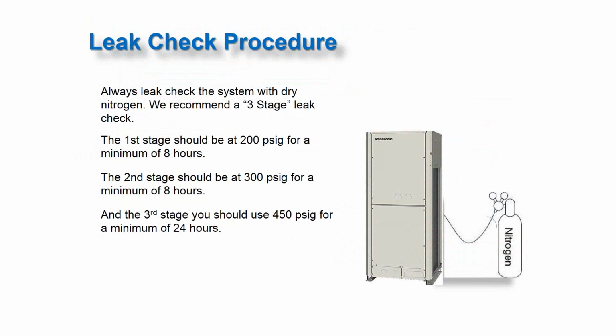Okay, leak check procedure. Very, very, very important when doing commissioning. When you're all done with your install, before you do startup, leak check your refrigerant pipes to make sure there's no leak. That's one of the biggest problems with VRF and ductless: refrigerant leaks in your piping system. So it's very, very important that you do the work on the front end to make sure that you're not going to have to deal with leaks in the future.